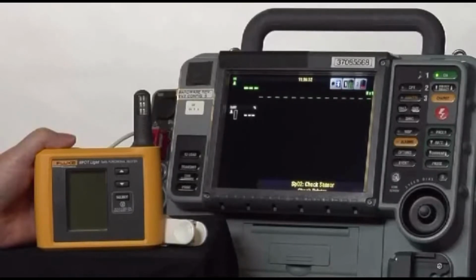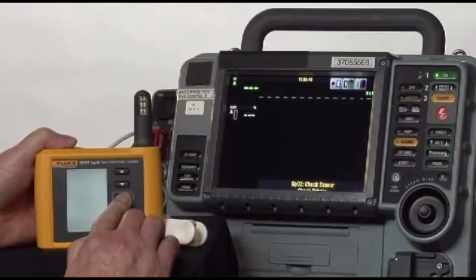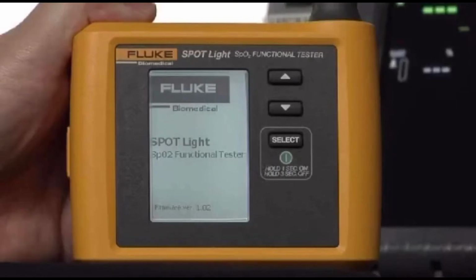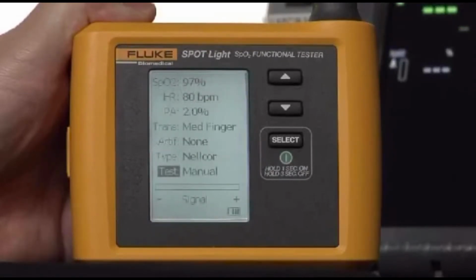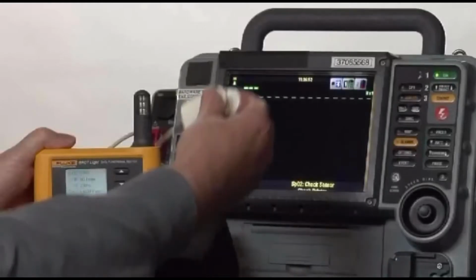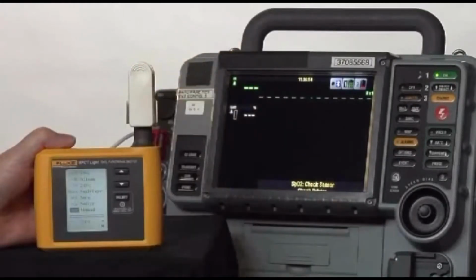In this case, we find the device turned on. It's a defibrillator, and we will turn on our Spotlight SpO2 functional tester. Wait for it to go through its self-check. And we will then connect the oximeter sensor from the medical device, and we'll watch this bar down at the bottom. It's called the signal strength bar, and you can see that it has a good signal, and you will begin to see the display on the screen of the defibrillator.